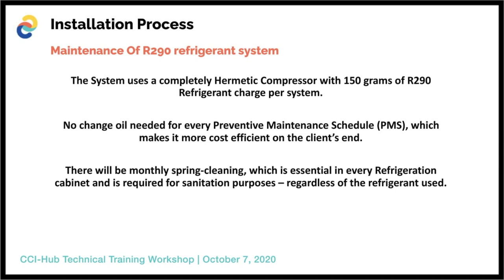Maintenance of R290 refrigerant system. The system uses a completely hermetic compressor with a 150 grams of R290 refrigerant charge per system. No oil change is needed for every preventive maintenance schedule or PMS, which makes it more cost efficient on the client's end. There will be monthly spring cleaning, which is essential in every refrigeration cabinet and is required for sanitation purposes, regardless of the refrigerant used.